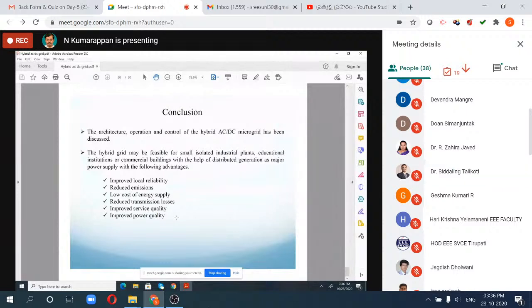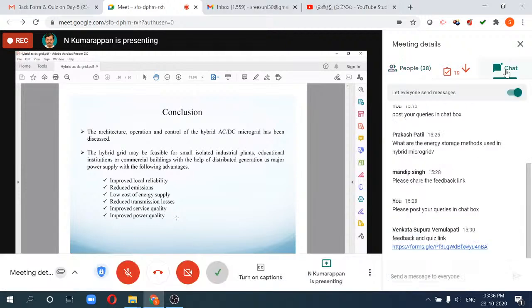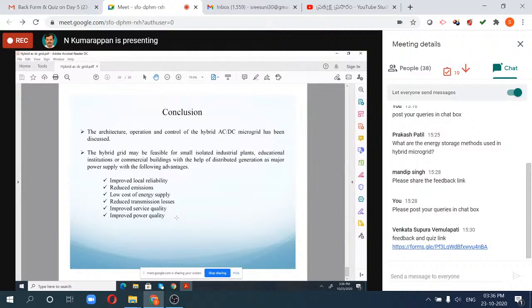That's why I explained in the last part that improved power quality plays a very important role. Once you introduce reactive FACTS devices, it not only compensates the reactive power but also affects the real power. Compensating the reactive power not only maintains the voltage but also reduces the losses. This is very important - most people think losses depend only on the real power, but that's not so. Even reactive power changes affect the losses. So once you concentrate on improving the reactive side, the losses reduce further. That is also a very important message.